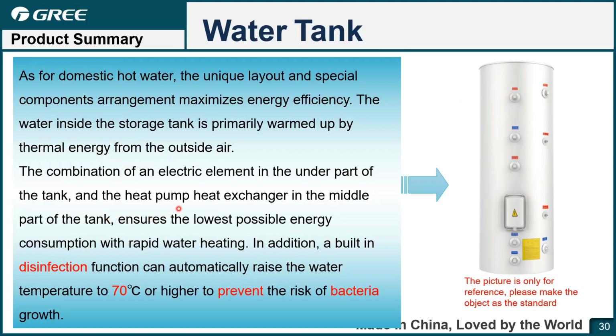And here is the water tank, optional, and this picture is only for reference. Maybe in different countries, the size and the design may be a little bit different. You can see there are many connections for the water pipe. For this tank, there is a double coil. These two are for the solar energy. These two are for the heat pump water circulating, and this is for drainage. And here is the cold water in and hot water out, and these two are for the temperature sensor.